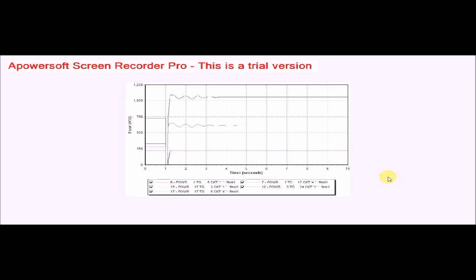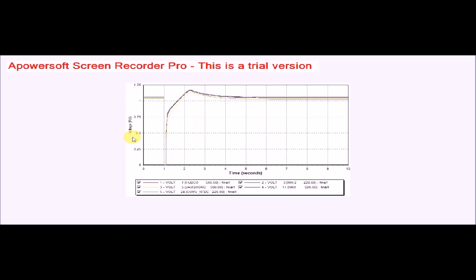In the stability analysis, we analyze whether, after a fault at a particular bus causes a line outage and is then removed with the line returned to service, the system returns to its original synchronization. In the first case, we introduce a fault at the Hubco bus at one second of simulation time. We see that the corresponding buses achieve synchronism after three seconds of fault removal. The real power chart and per-unit voltage chart both confirm that original values are restored after three seconds — the system is stable in case one.